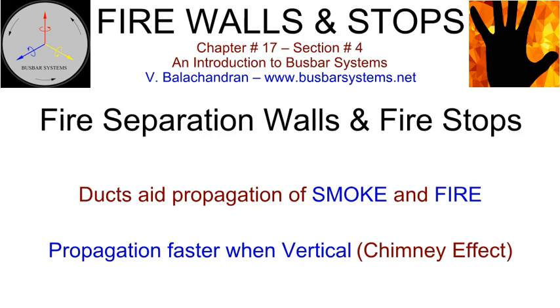Whenever an enclosed bus crosses a wall that separates two ambient areas, an opening is provided on the wall for the crossing. It is recommended that the opening and embedment, if any, be designed in consultation with the manufacturer of the enclosed bus. The manufacturer of the enclosed bus will supply a wall frame assembly to suit the opening and embedment, with the necessary components, to meet the specification requirements.